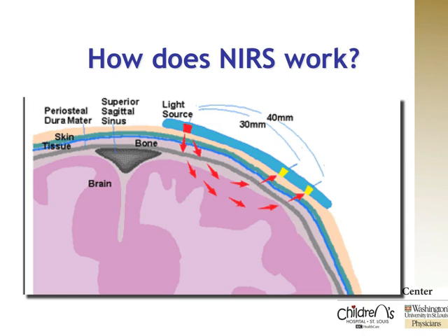And when we apply this to the patient, in this diagram it's on the head, the light goes into the tissue, some of it's reflected back and picked up at the sensors. And the light that is picked up by the near sensor hasn't traveled as deep into the tissue compared to the light that is picked up by the far sensor.